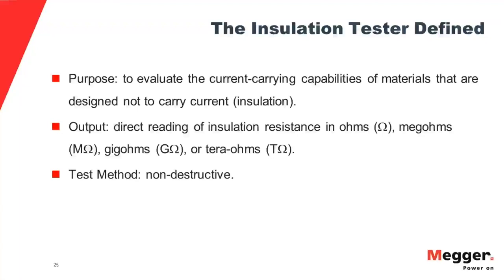So these testers are non-destructive. That's a main differentiation from a high pot or a dielectric strength tester, which is more commonly called a high pot. High pots function in very much the same way that an insulation tester does, but they have more power. They're not concerned with measurement. They're concerned with killing the weak, taking something out of service before it can do damage in service. So always keep that distinction in your mind when you're dealing with instrumentation, an insulation tester versus a high pot.